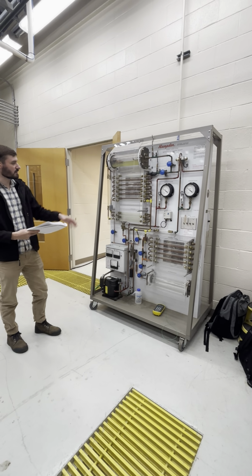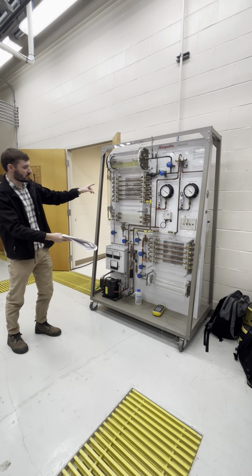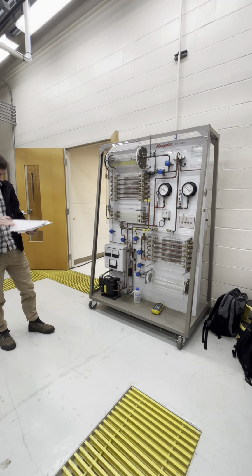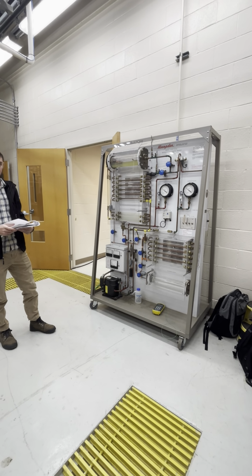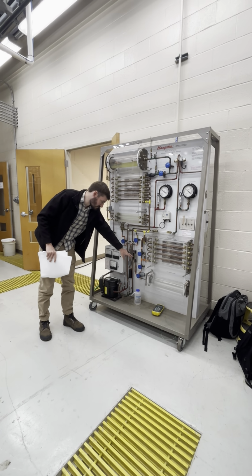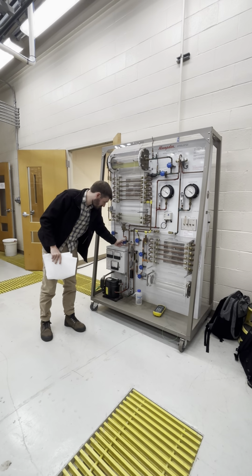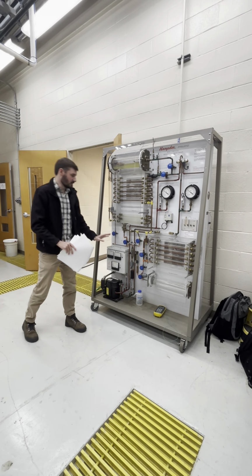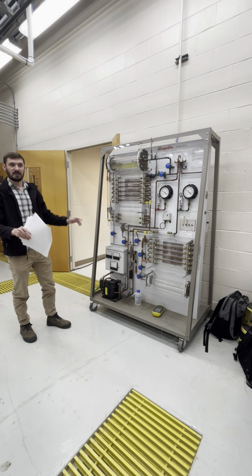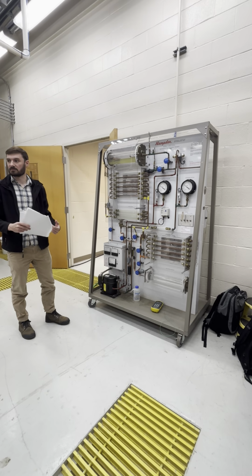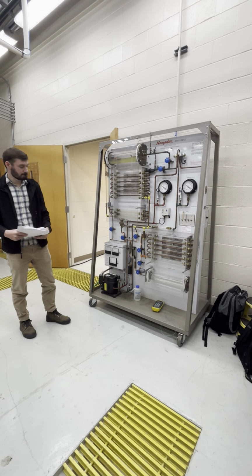And again, we're doing this with both fans on, and then just the condenser fan on. We'll flip this off over time, okay? That makes sense? So we're just slowly allowing this to get to 45, and slowly opening this while not allowing it to flood. You let it get to steady state, you take all your measurements. Flip the fan off, let it get to steady state again, take all the measurements. Pretty straightforward, okay.